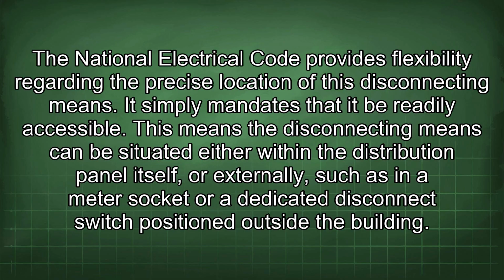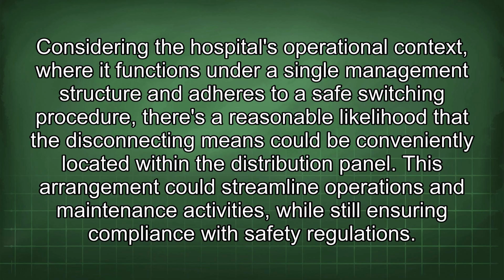The National Electrical Code provides flexibility regarding the precise location of this disconnecting means. It simply mandates that it be readily accessible. This means the disconnecting means can be situated either within the distribution panel itself or externally, such as in a meter socket or a dedicated disconnect switch positioned outside the building. Considering the hospital's operational context, where it functions under a single management structure and adheres to a safe switching procedure, there's a reasonable likelihood that the disconnecting means could be conveniently located within the distribution panel. This arrangement could streamline operations and maintenance activities while still ensuring compliance with safety regulations.